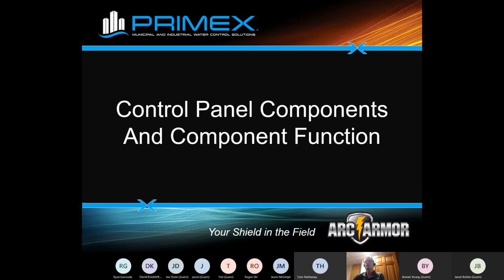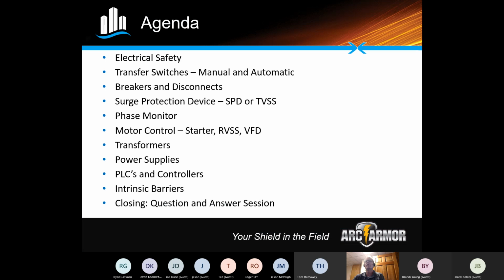The title of this presentation is Control Panel Components and the Component Function. We're going to spend a little bit of time going through the following components. We're going to start with electrical safety, then jump into transfer switches, breakers and disconnects, a little bit on surge protection, phase monitors, motor control, transformers, power supplies, and then go into PLC controllers, barriers for UL 698 applications, and then the closing has questions and answers. But this is pretty informal, so if there's a component that you would like to discuss that's not on here, by all means ask, and we can spend a little bit of time on that.